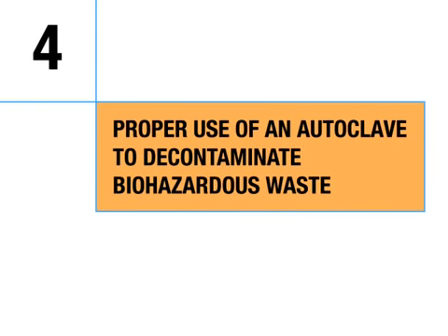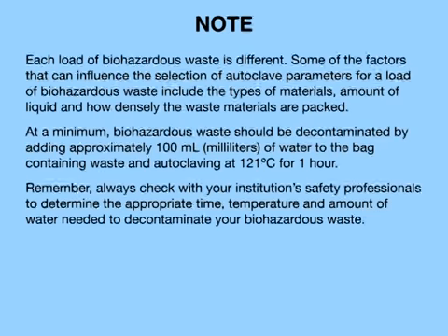Proper use of an autoclave to decontaminate biohazardous waste. Note: each load of biohazardous waste is different. Some of the factors that can influence the selection of autoclave parameters for a load of biohazardous waste include the types of materials, amount of liquid, and how densely the waste materials are packed. At a minimum, biohazardous waste should be decontaminated by adding approximately 100 milliliters of water to the bag containing waste and autoclaving at 121 degrees Celsius for 1 hour.